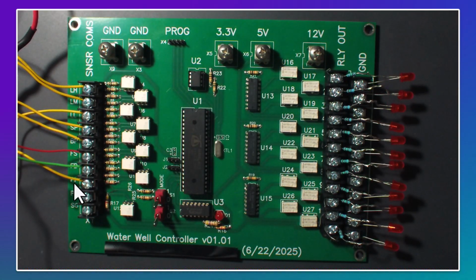In fact, most of these are going to be changing. I'm moving away from switches for the level of water in the well and going to a submersible pressure transducer that'll be put in the bottom of the well. Out at that well house I'll probably have a propeller chip or another type of controller interpreting the pressure to get the level of the water, and also the flow sense. I'm moving away from the little propeller type I have in there, going to ultrasonic flow sensing, so I'm moving away from these two as well. These will still be there for indicating whether the power's on or off.